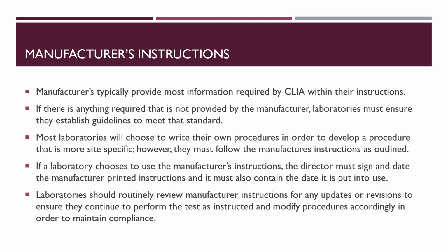For example, a kit may say that you can use plasma or serum, but this particular laboratory may only draw plasma tubes because that's primarily what they use. So those details need to be spelled out in the procedure as far as what the laboratory's expectation is for their facility. If, again, the laboratory does choose to use the manufacturer's instructions, then the laboratory director would have to sign off on that, and of course that does have to be dated.